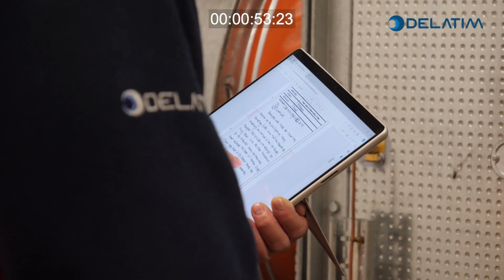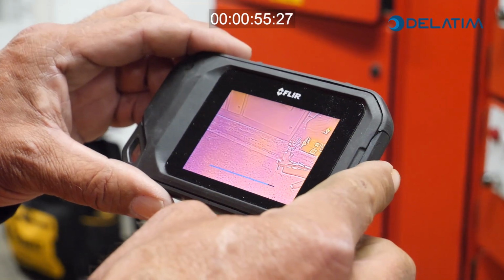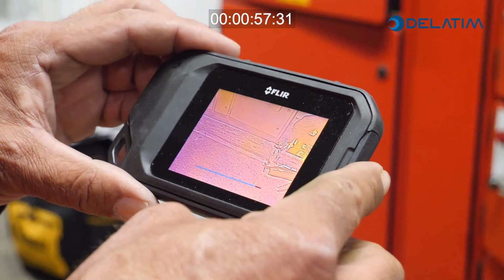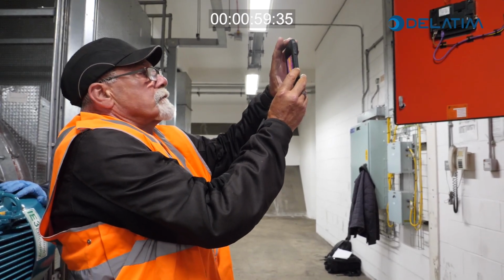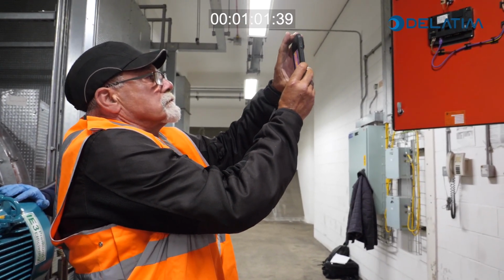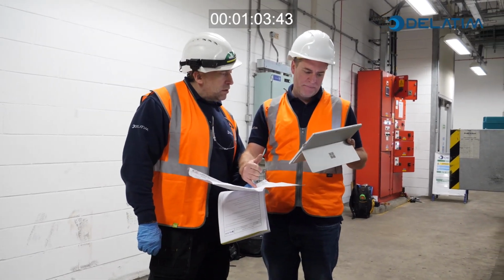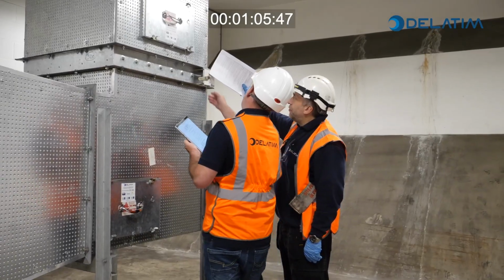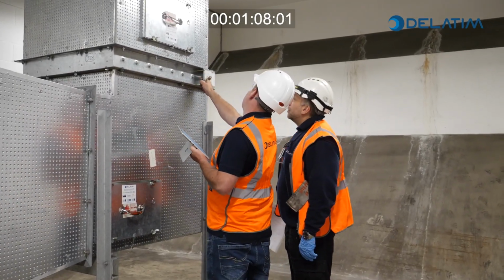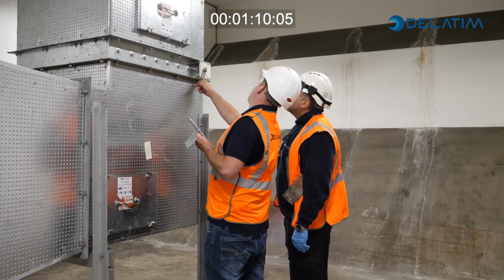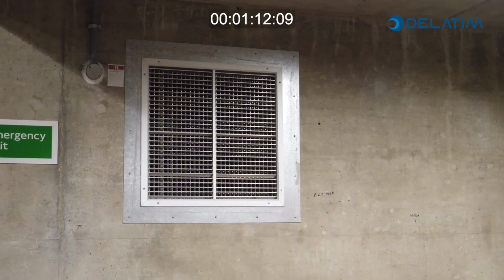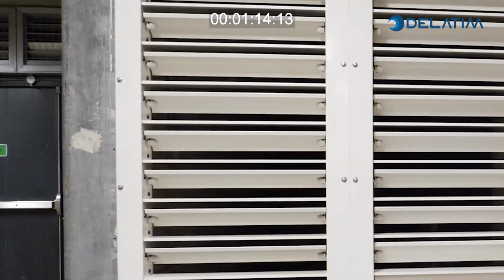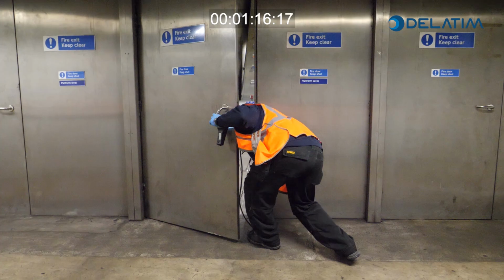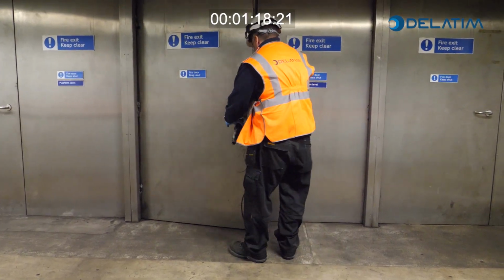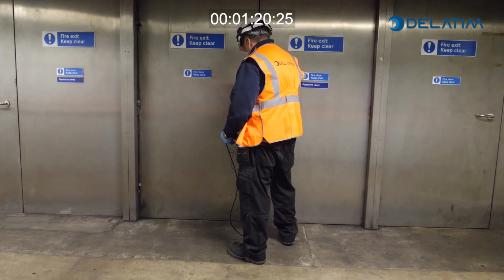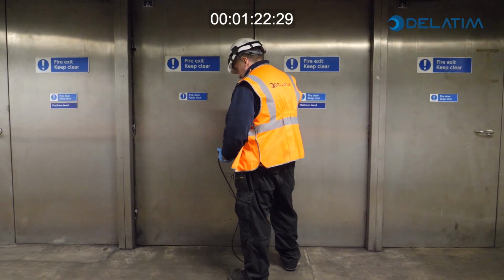On completion of the midlife intervention of all assets, Delatim undertake testing and commissioning of the stair pressurisation systems. This is to ensure that the systems perform to standard as a whole. Testing and commissioning include air volume testing at the fan, balancing the system supply air at each supply grill across the staircase, air pressure differential readings between each door into the staircase and lift shafts.